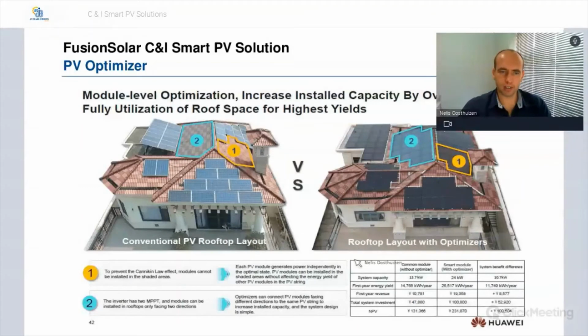So next slide is, again, it's just a module level optimization. It's just showing that increase installed capacity by over 70%. So it's a roof with different orientations and angles. So if you were not using optimizers, you could only maybe use one segment of the roof, or use one string for one segment and a second string for another one.